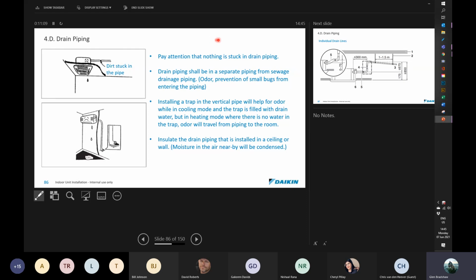Okay. Pay attention that nothing is stuck in the drain piping. We've seen, in the years that I've been doing this, and I must say it's happened to me, if you're busy gluing piping and you're applying too much PVC glue, often you can actually form a blockage. So make sure that there's nothing stuck in the pipe, no glue plugs, and nothing shoved in there because somebody was busy getting rid of their cigarette packet or something while you weren't watching.